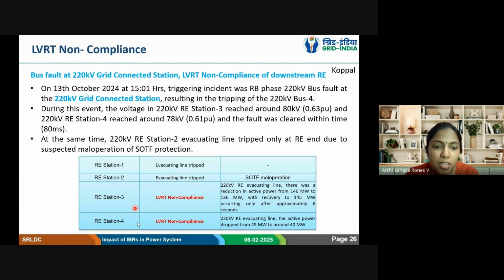Later, for the other RE stations, that is RE station 3 and 4, which were connected to that pooling station, we didn't observe tripping of the evacuating line, but LVRT non-compliance was observed. For example, station 3 was generating around 146. After the event, it should have recovered within one second, but there was a delay in the recovery. It took almost 6 seconds. And in RE station 4, there was some tripping also. A few WTGs, like 1 or 2, got tripped, maybe 3 megawatt.